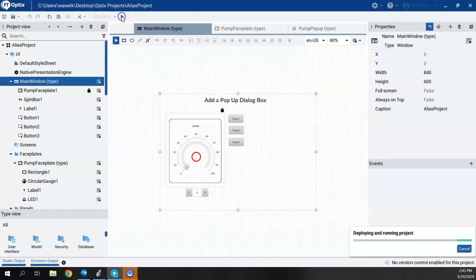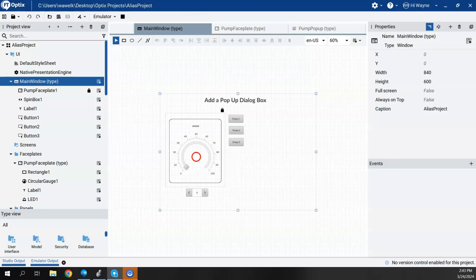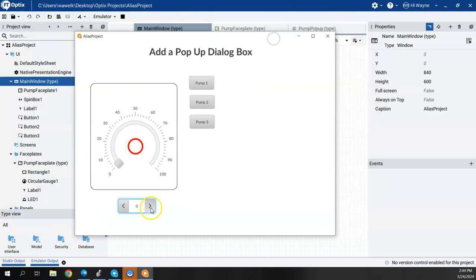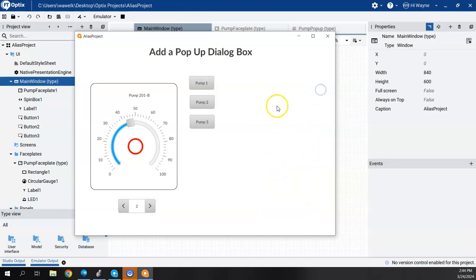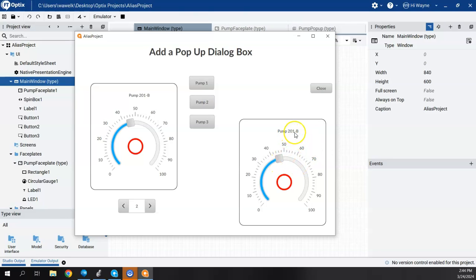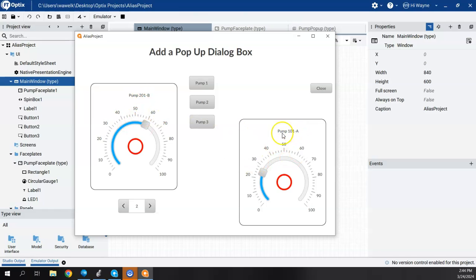I'll save that and start the emulator. We can see pump one, pump two, and pump three information. If I click on the pump three button, the popup appears in the bottom right corner showing the exact same data as pump three. If I change the value here it changes in the popup. I close it, open pump two — here's pump two's data; if I change it here it changes there. Then close it and open pump one — here's pump one's data, pump 101A. So pump two and pump one are both working correctly.